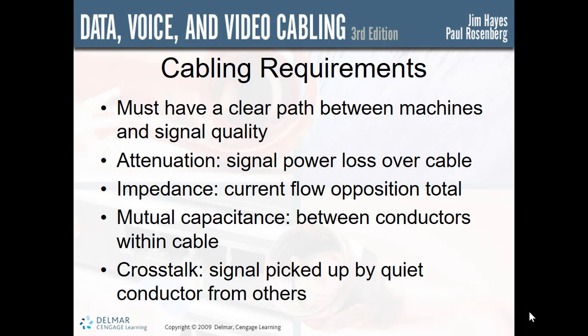As mentioned, capacitance is the most common element of attenuation. This is the capacitance between the conductors within the cable. Capacitance is a big factor because it causes the cable to filter out high frequency signals. Data transmissions are square wave signals, and when the capacitance is too great, it has a tendency to round off that digital signal. When data signals have a clear square wave, they're easily intelligible to the receiver. If, however, the signals become rounded, then they're confusing to the receiver, causing what we call a high bit error rate, or causing the data to be received in error, and therefore we just discard the whole signal.